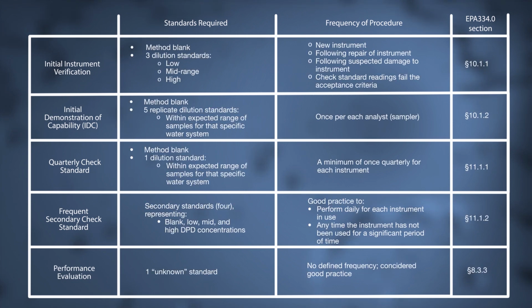Now that we've learned how to prepare and measure a chlorine dilution standard, we need to learn how to decide what concentration is needed for the quality assurance test we want to perform. Chlorine dilution standards can be used for multiple quality assurance processes, including routine quarterly checks, initial demonstration of capability, and initial instrument verification. This table shows the number of samples needed for each type of quality assurance test and what dilution concentration is used.